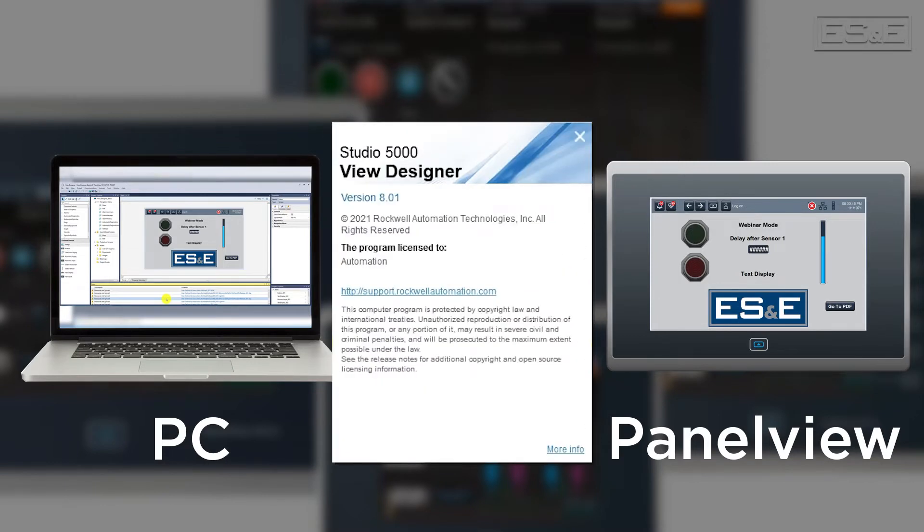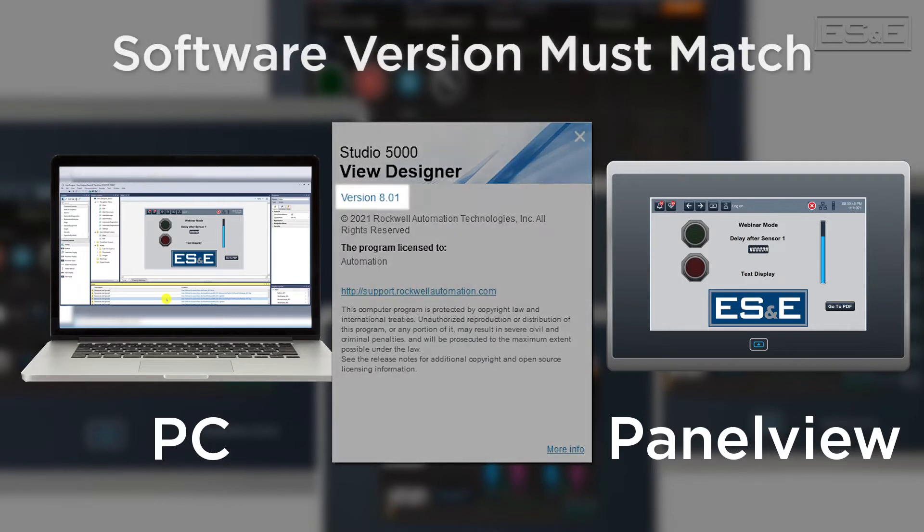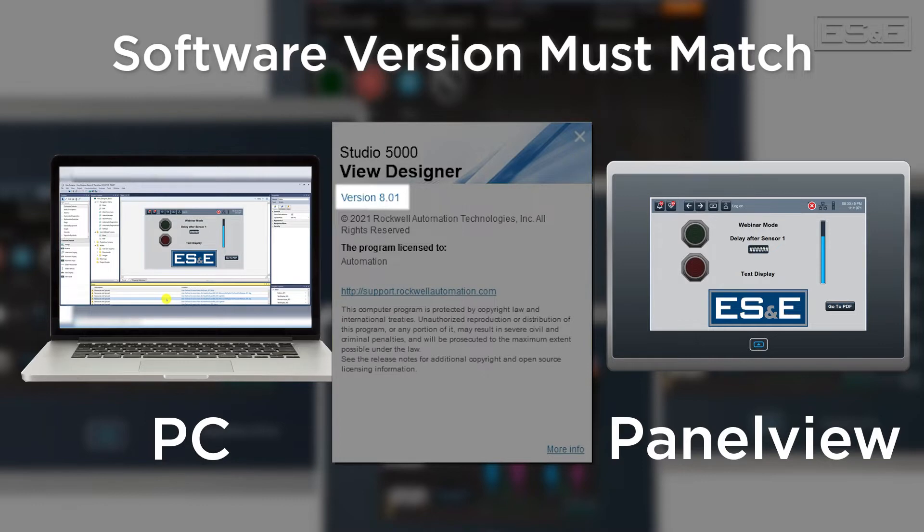For all Studio 5000 software, Logix and View, you need to ensure that you have the same major revision software on your computer as the major revision of firmware that's on the device.